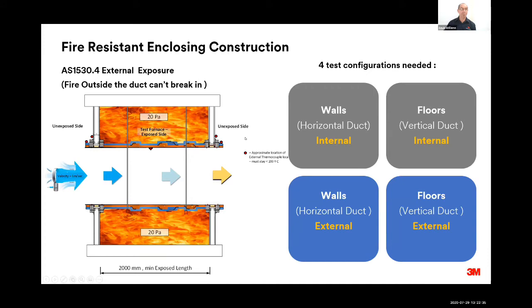And also we have external exposure, where the duct is exposed to fire from the outside, and we're testing to make sure that fire doesn't break in. Again, we're measuring structural adequacy, integrity, and insulation. And so in total, there are 4 configurations that are usually needed. So there's internal and external for both walls and floors, or horizontal and vertical orientations.